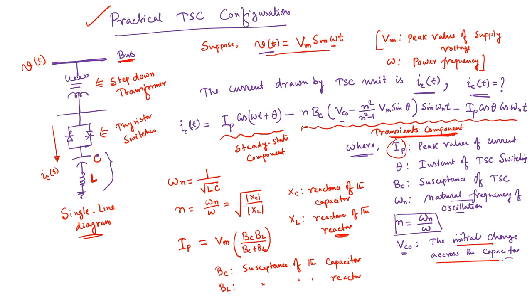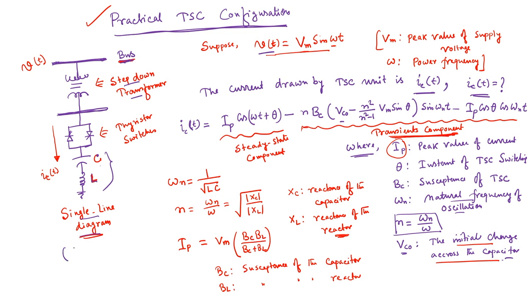Looking at the practical TSC configuration, it consists of a step-down transformer for stepping down the voltage from the transmission level to a much lower voltage at a particular bus. Then we have a bi-directional switch, a fixed capacitor, and a small reactor. The role of the reactor is primarily to restrict the current during switching and also to restrict the high di/dt value during switching. This is the single-phase configuration of the TSC.